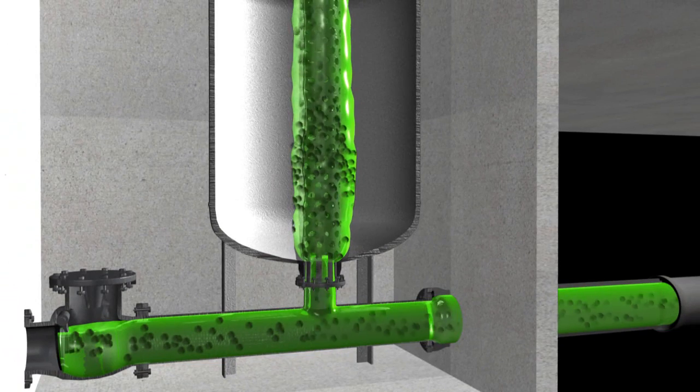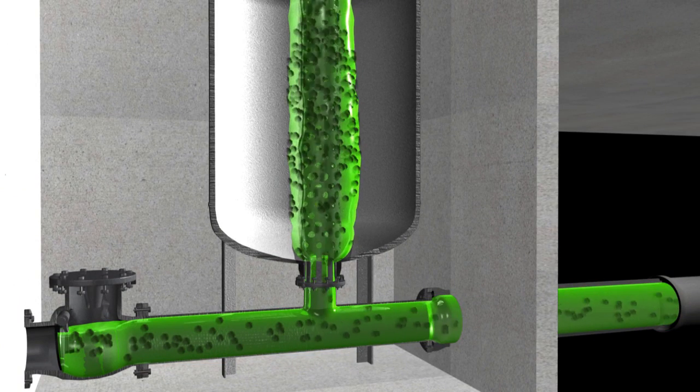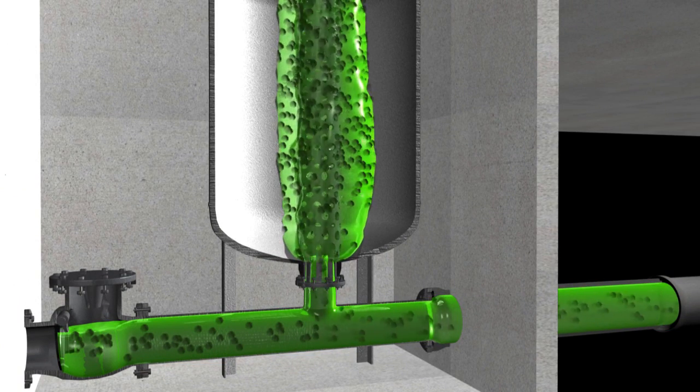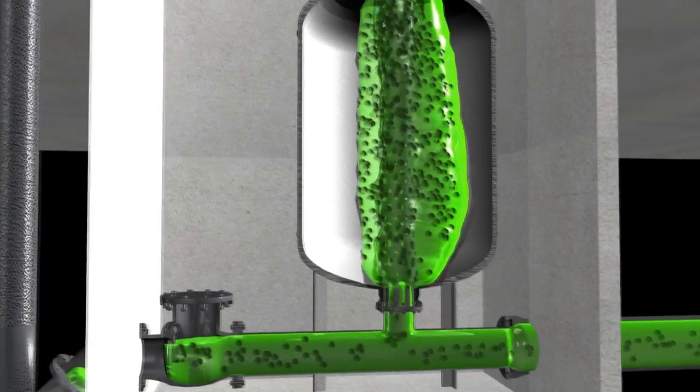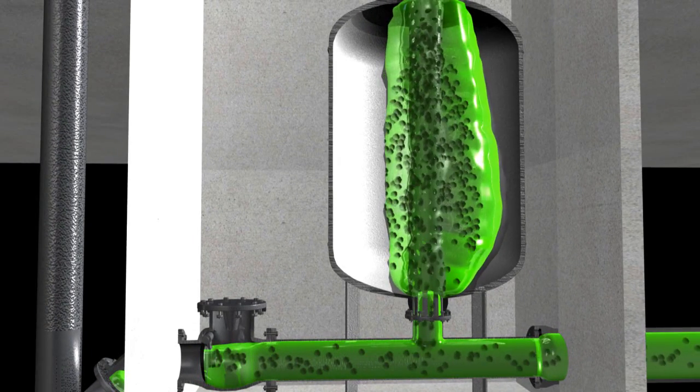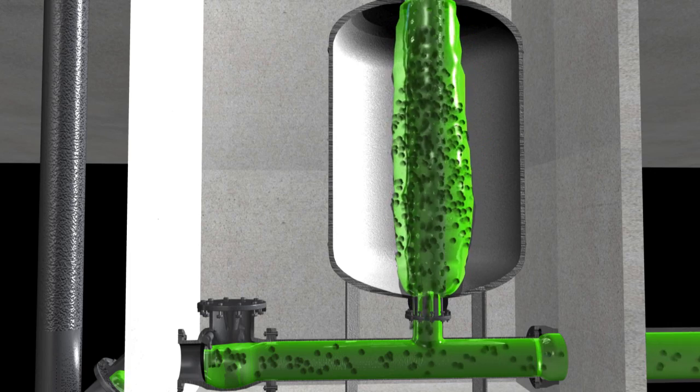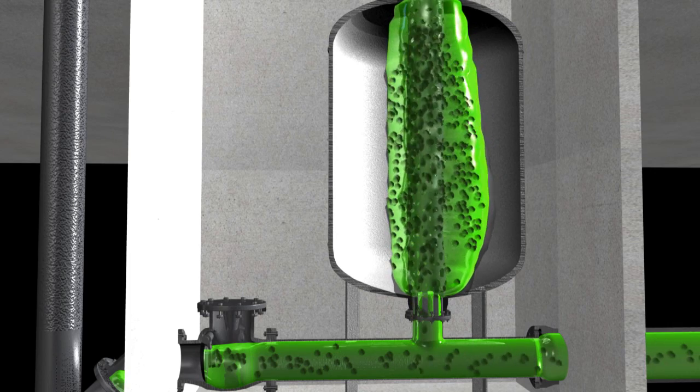As the fluid starts changing direction due to pump loss, sewage is now redirected up into the tank through the column, filling the bladder. The bladder compresses the gas in the tank, absorbing the energy of the reverse flow, oscillating until the fluid energy rests.